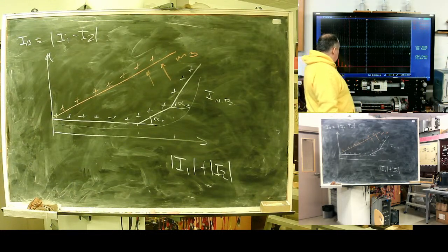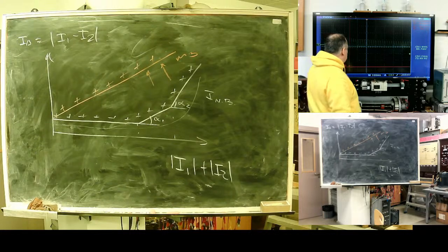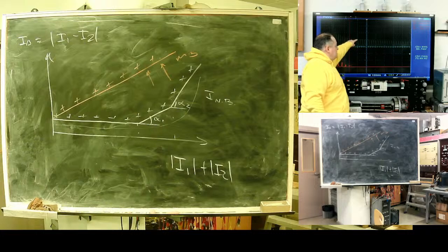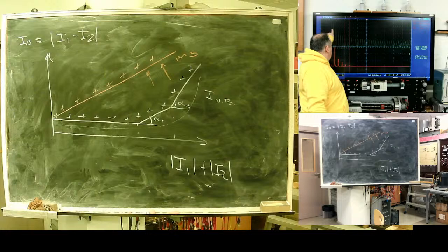See, they should go through the Fourier filter. You will have a manufacturer's advice for the protection. You need to select this characteristic to prevent false operation from approximately this side, because your Fourier filter will most probably cut this component.